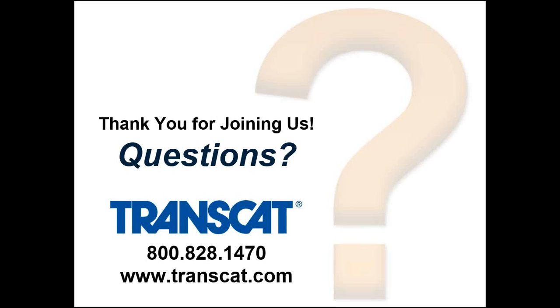Now, optimally, or ideally, it would be great to have the calibration support the test points exactly as the instrument's used, and that would be a custom cal for every instrument, but that's very costly. So for the most part, going to a default calibration that follows the test points or methodology of the manufacturer is typically what we do, unless that doesn't make sense. And so that unless it doesn't make sense part is where you may need some help in making a decision on whether it makes sense or not. If it smells funny when you're looking at it, if it looks funny, then that's when you raise the question. If it seems to be a sound procedure that's following good test points, then that's fine.